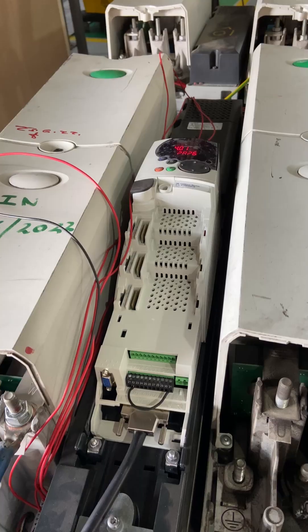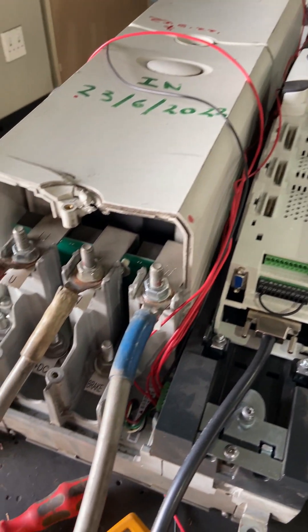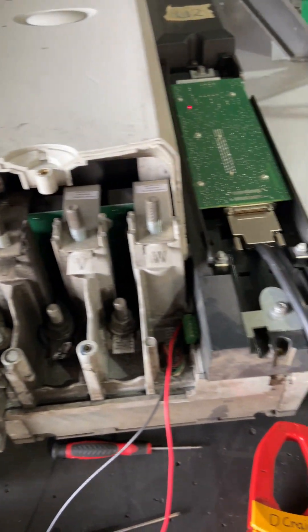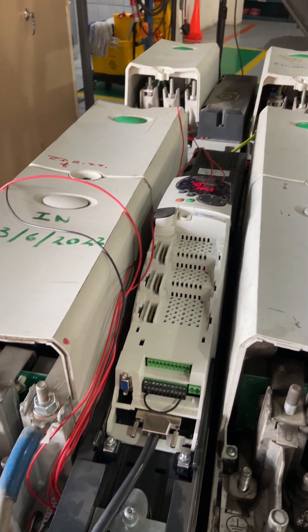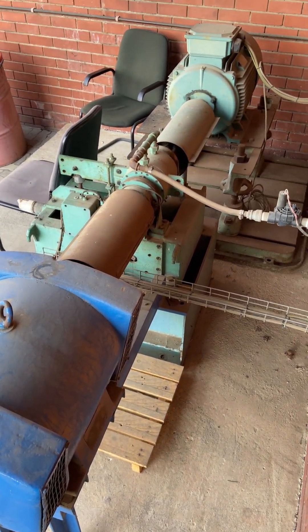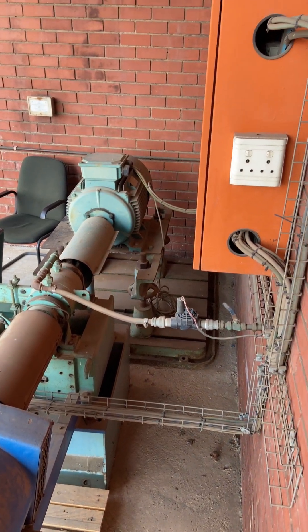Here we're load testing. That is your master and it is connected to a slave on the right-hand side, so that's a follower pod. There are the rectifiers up top, and then outside over here is our dyno with a 500 volt motor. The green one is 400 volts, and that's a water load — there's a pump in the middle.